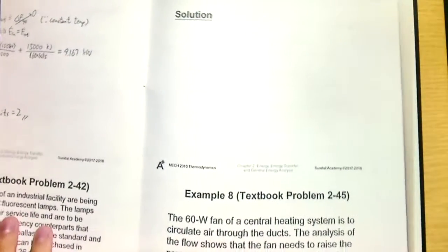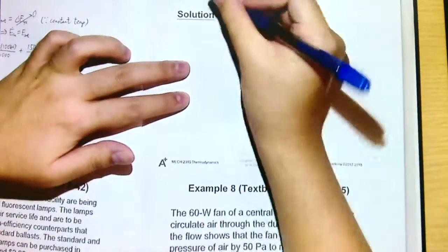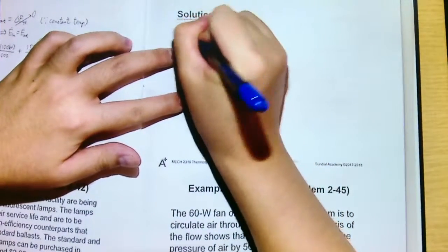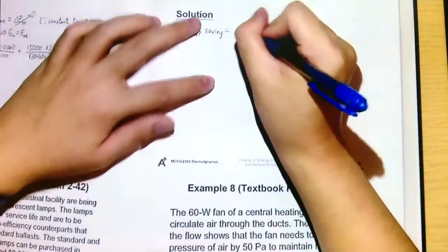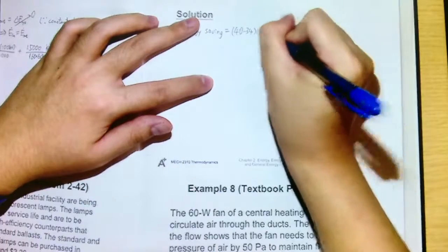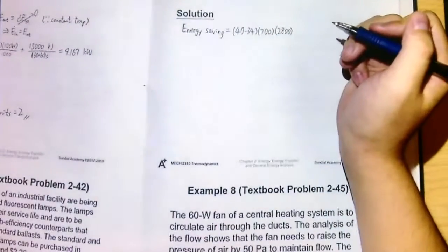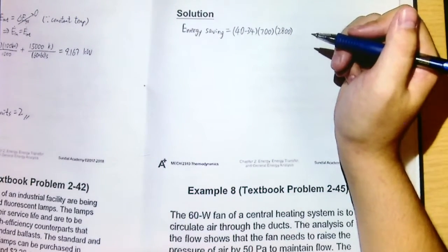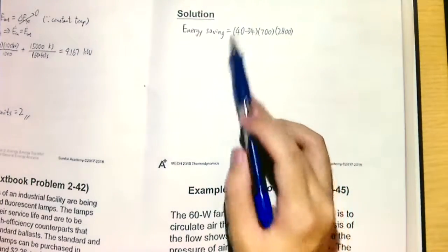Let's see how we can do this kind of problem. So how can we know the energy that we have saved? Okay, we calculate this one first. Well, we have assumed that both of them are operating in the same operating hours, and the only difference is that the rated powers are different. So we don't need to divide this into several steps. Okay, we can just write 40 watts minus 34 watts times 700 light bulbs. Okay, in 1 year it operates 2,800 hours. Okay, and here this one should be watts. 40 minus 34, both of them are watts, so this term should be in the units of watts.